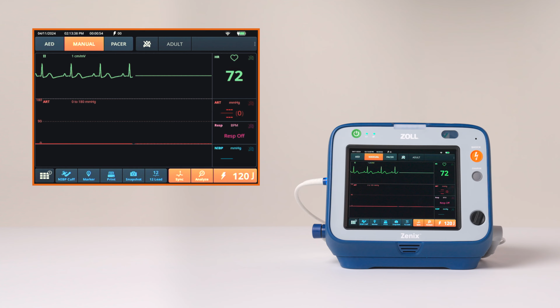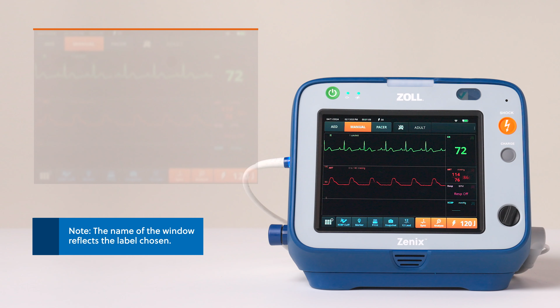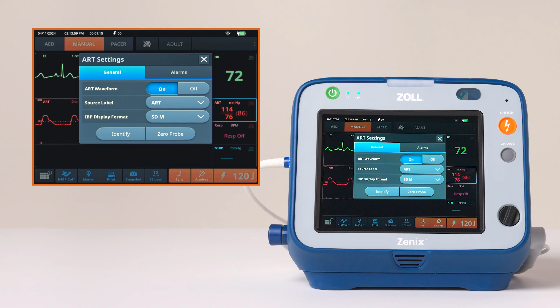When the IBP Setup label window appears, select the appropriate label. For this demonstration, we have labeled it as ART. The invasive pressure waveform and numeric automatically appear at this point. Highlight and select the ART window to adjust general settings and alarms. Selecting the Identify option changes the sensor LED bar from green to blinking white. This helps to identify the IBP cable when you are using multiple lines.